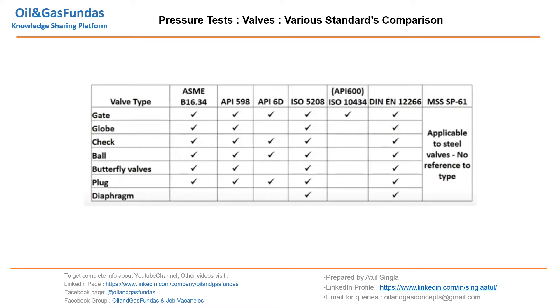Let's have a look at various standards which talk about shell pressure test. These are the valve types which we have already discussed, and these are the standards which talk about pressure test, examination, and inspection. As per ASME B16.34, this test is required for gate, globe, check, and ball valves — except for diaphragm valves. Similarly, API 598 also states this test is required, and API 6D says it is required for gate, check, ball, and plug valves.